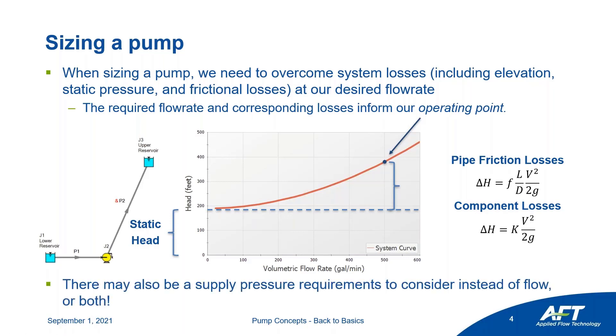It's important to understand what goes into the system curve because your pump is never going to operate in isolation — you're always sizing that pump in the context of a system to meet a specific operating point. Generally these pump requirements are based on flow rate, but it may also be important to consider supply pressure requirements. For example, if you need a particular pressure at an upper reservoir, you may have to consider that in addition to your flow rate requirements.